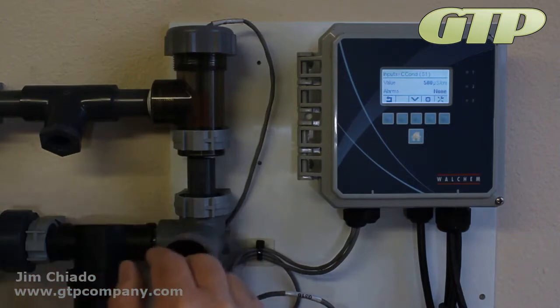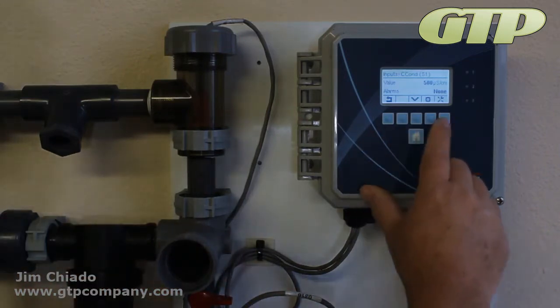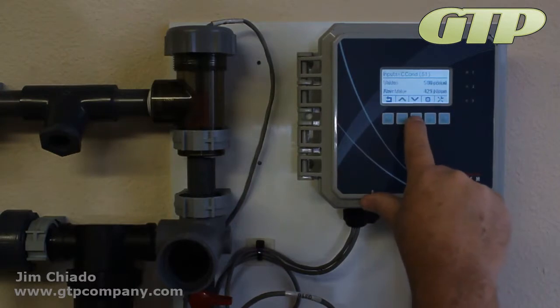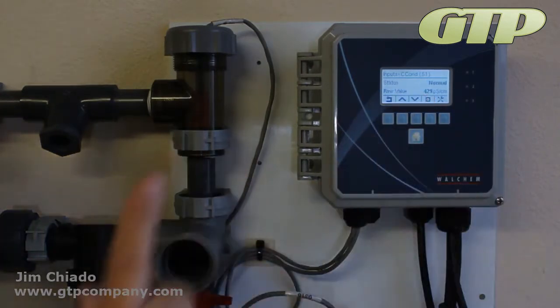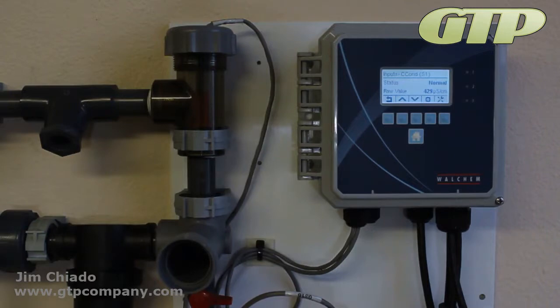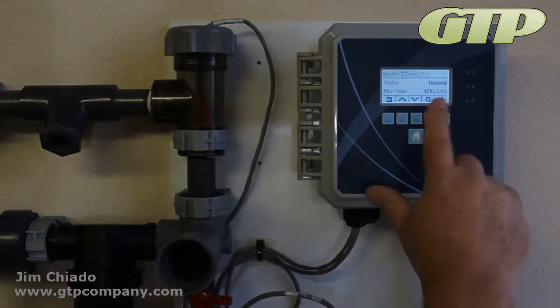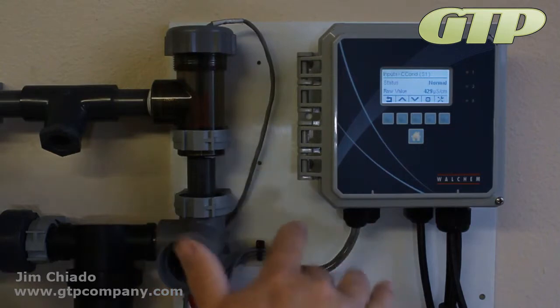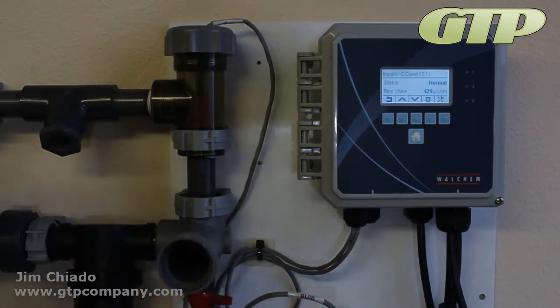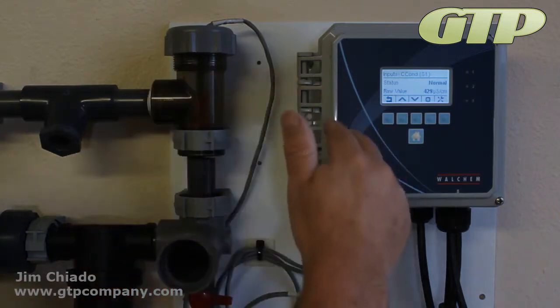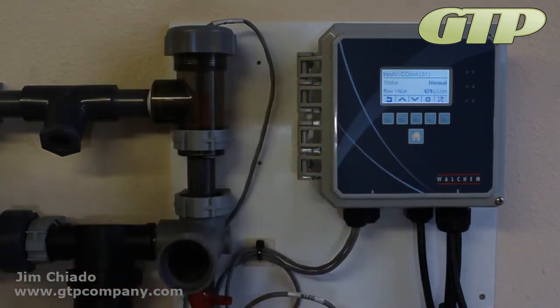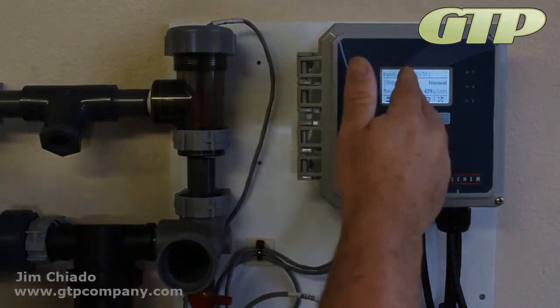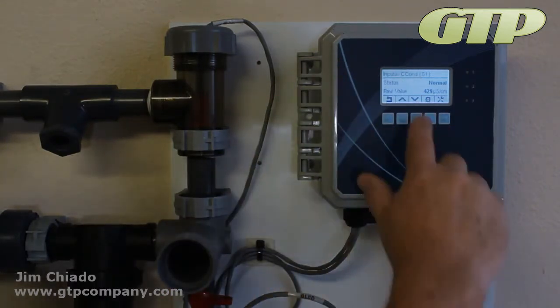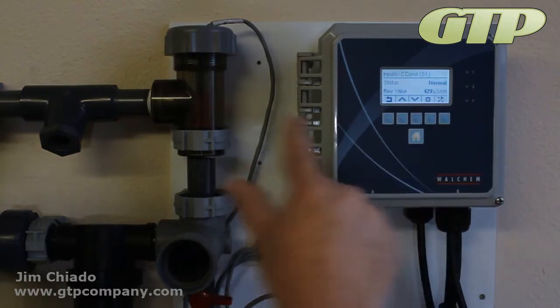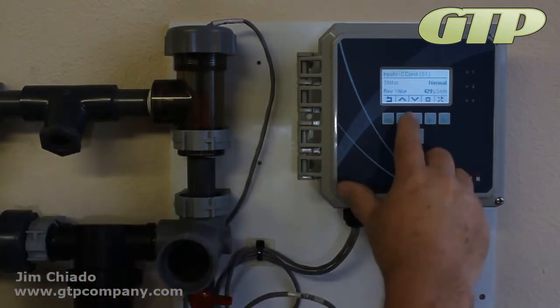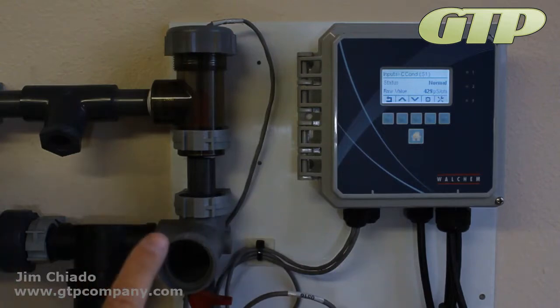The problem that most people see is that it says out of range and stuff like that. So what we're going to do here is come in and look at the raw value, and that's typically what happens when they get out of range. The raw value is what it is. It's what the sensor believes the solution to be. The factory puts in a calibration factor of 1.5 times whatever the raw value is. So if you see out of range, you're trying to go past 1.5 times what it thinks the raw value is. If it's that, the sensor's going bad, and the sensor needs to be replaced.